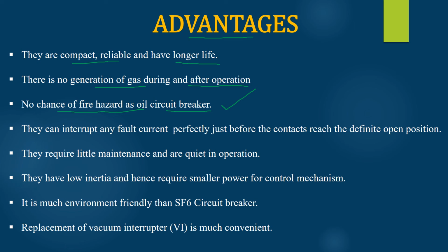They can interrupt any fault current perfectly just before the contacts reach the definite open position. They require little maintenance and are quiet in operation. There is no noise created during the operation. They have low inertia and hence they require smaller power for the control mechanism.